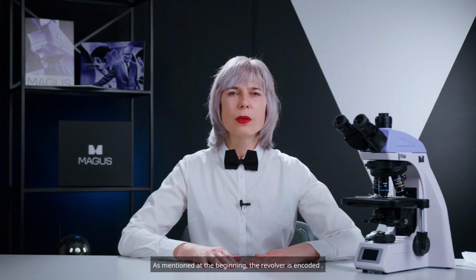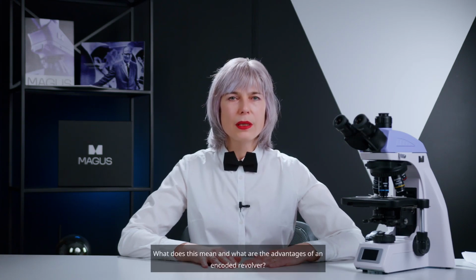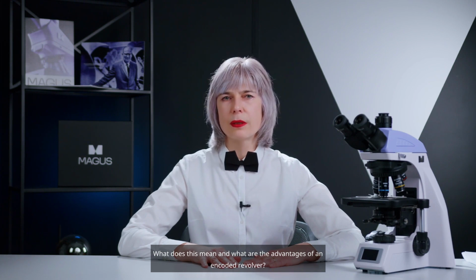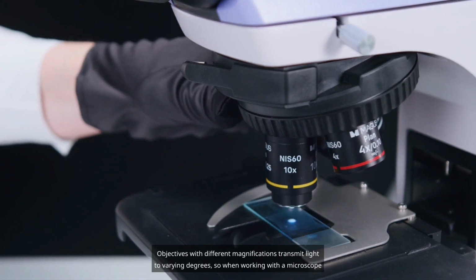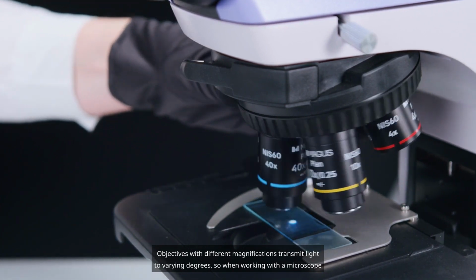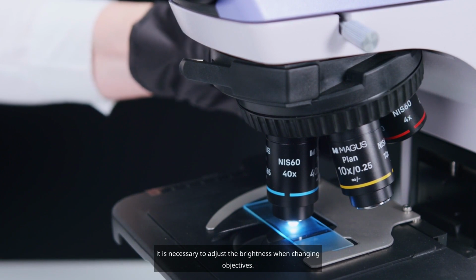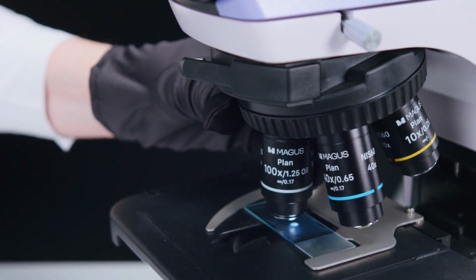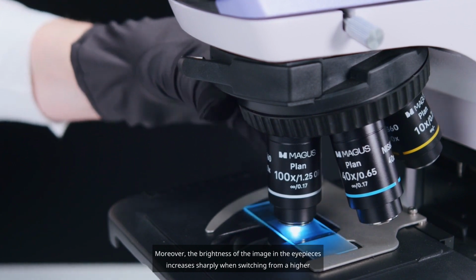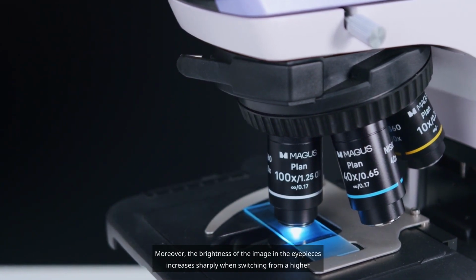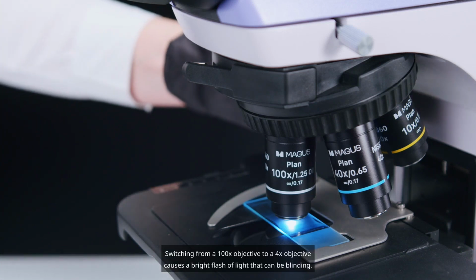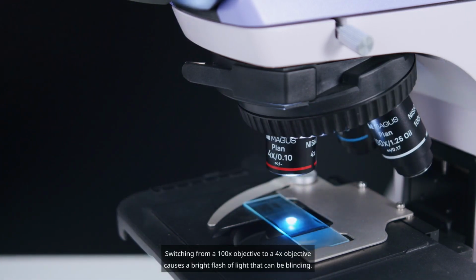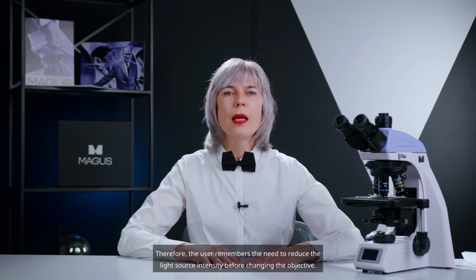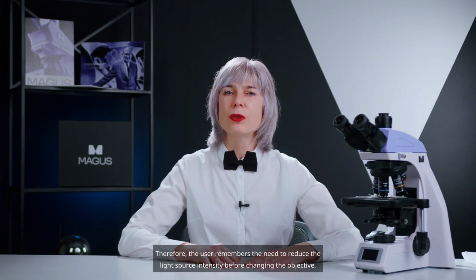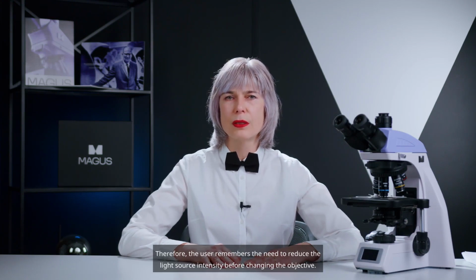As mentioned at the beginning, the revolver is encoded. What does this mean? And what are the advantages of an encoded revolver? Objectives with different magnifications transmit light to varying degrees. So, when working with a microscope, it is necessary to adjust the brightness when changing objectives. Moreover, the brightness of the image in the eyepieces increases sharply when switching from a higher magnification objective to a lower magnification objective. Switching from a 100x objective to a 4x objective causes a bright flash of light that can be blinding. Therefore, the user remembers the need to reduce the light source intensity before changing the objective.